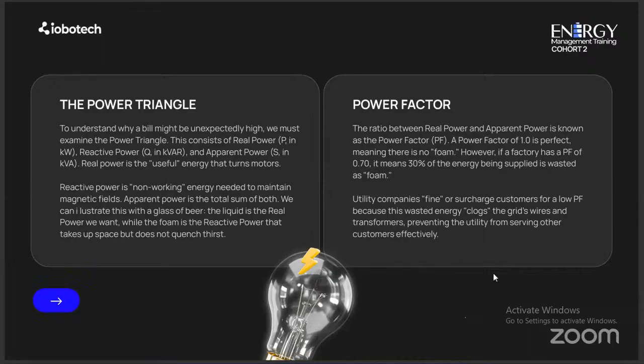But in a situation where you use an inductive load and an inspection is carried out on your meter, and it's discovered that your power factor is below the acceptable threshold—for instance, in Nigeria the acceptable threshold for power factor is between 0.85 and 0.9 or 0.99—but if your power factor is below 0.8, say 0.7 or 0.75, it will flag your energy meter because of your inductive load. In that situation, your demand, your KVA, would be considered in order to bill you correctly.